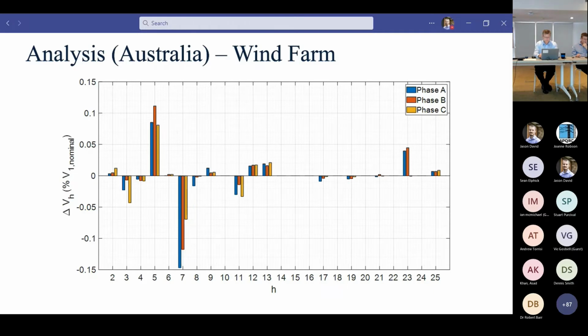We were given this data anonymously, or the actual details were made anonymous. But what we can see is that comparing pre-connection voltage levels with post-connection, at the fifth order we see a slight increase of about 0.1% across the three phases. For all others, the impacts are restricted to less than 0.05% of the nominal, other than the 7th, in which we actually see some attenuation, and so there's a relative improvement at the 7th. Reasons for this, we can't say for sure, since very little detail was provided to us about the actual installation itself. All we can see is simply the measurement data and the analysis that we've performed on it.